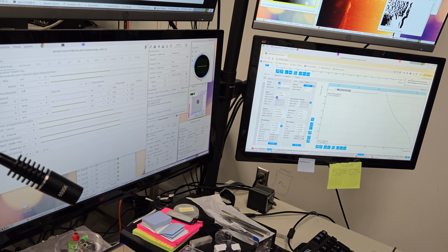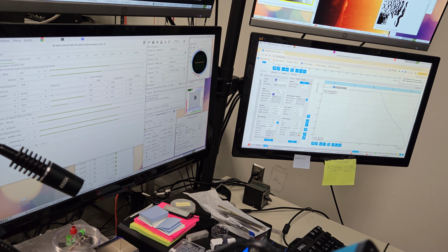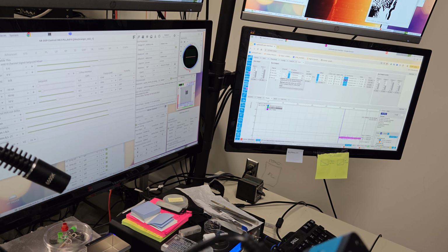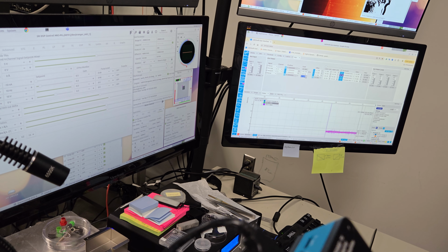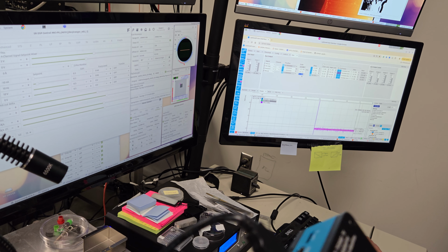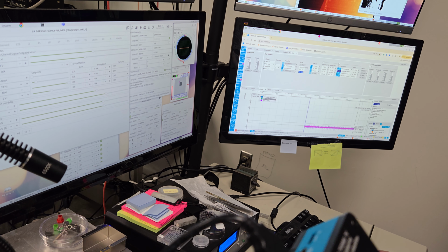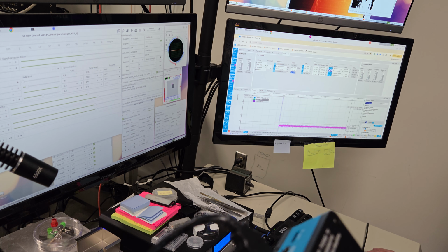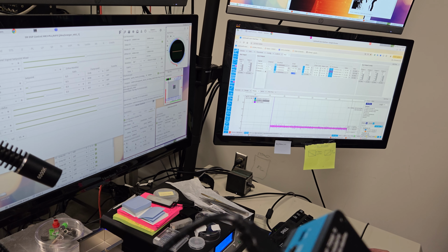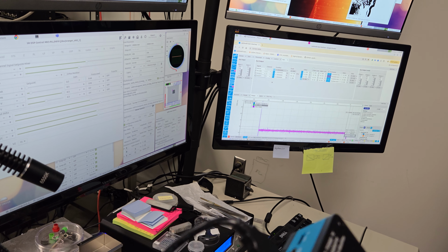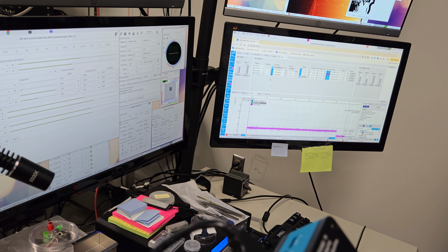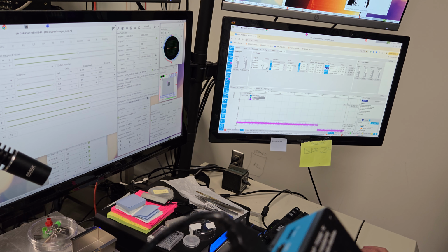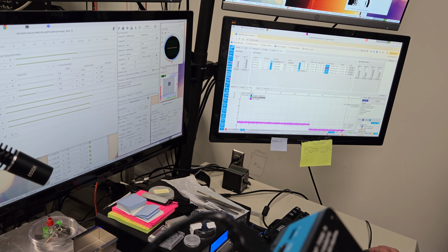Let's see if this works, turn it on. Okay, so this still works, right? Yes. So I think this should be the way to go because now it's manual. So you can set this value, put manual. I mean, can you set it? Okay, so now it's actually taken over by PID, which makes sense. Because initially it was this way. It was like this, right? So that means the value can be different.